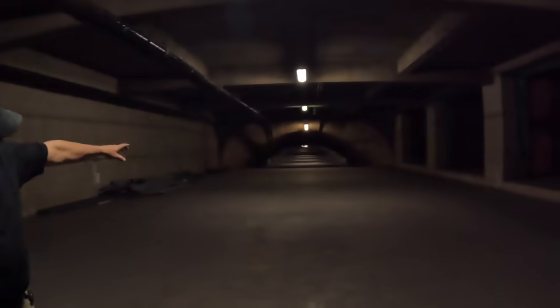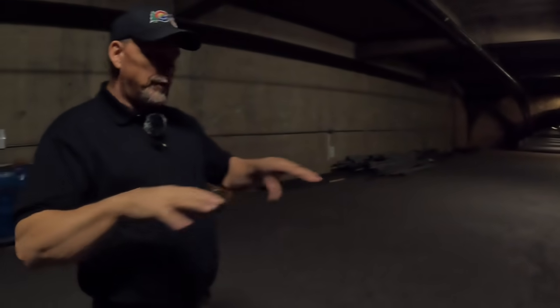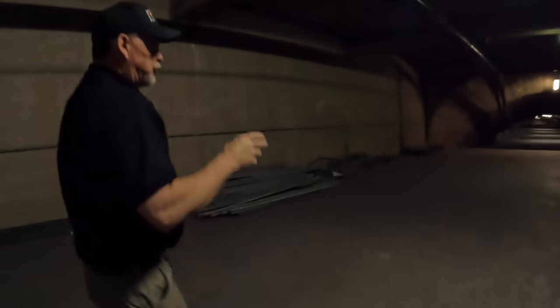So the tunnel ceiling through here, this goes all the way through, it's called a plenum. This will go all the way through to the end of the tunnel in both directions. Now the ceiling of the bore has an aluminum substructure, so when it gets to a certain temperature, it's going to melt and fall in on the fire. That's the concept. When that happens, the smoke comes up into this void, and we're able to suck it out with four large fans. Or we can supply air, and you can see throughout this plenum area, there are openings down to traffic. So if we supply air, that air will go down through the tunnel and push smoke and heat out to protect our firefighters.